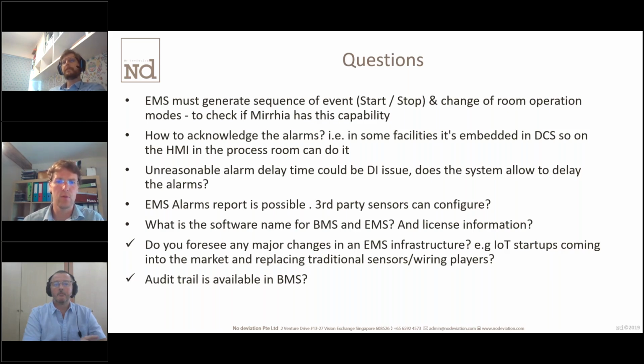And we've seen it a bit during the data integrity part, it's important that you keep monitoring. For example, if you forget to reset the alarm in production mode, you still have the data integrity, so you can still retrieve that data and reprocess. It's changing the alarm condition. I think Mirrhia can also start and stop those modes automatically with a timer, so you can say, I start the cleaning, therefore I have a 30-minute cleaning, and after it will automatically go into threshold one, which avoids the human error.